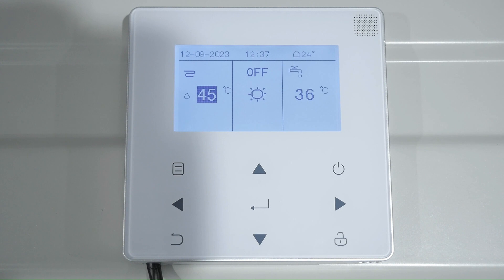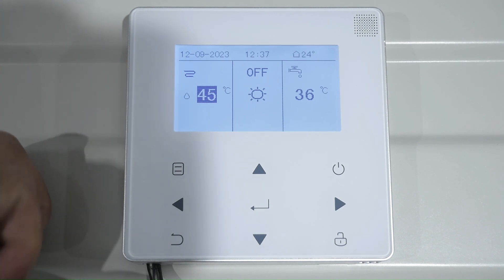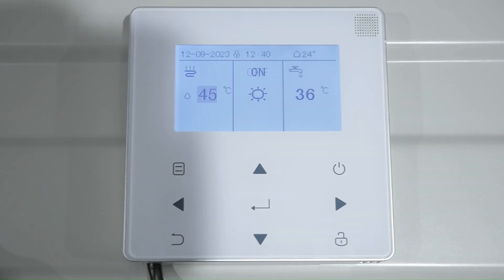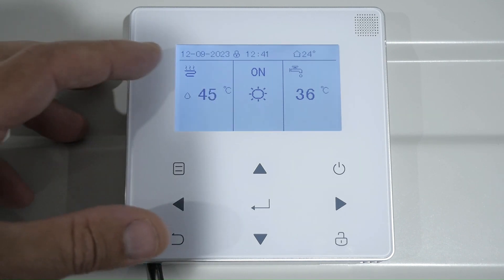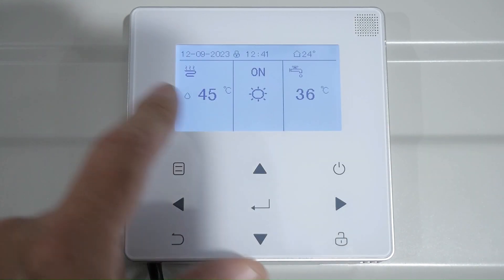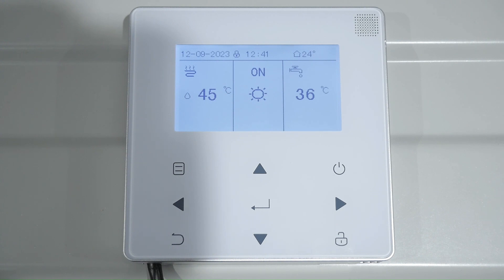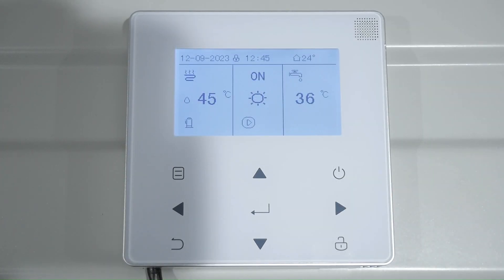You get demand on this stat which will in a moment bring the demand to the heat pump, which will in turn bring on the pump. You can see now the heating is on. It has let us know the heat pump is on and in function, and if you look for the squiggly lines you can see the function is on for the underfloor heating. In a moment you'll see a pump symbol come up to let you know the pump is starting, and then from that the compressor will run on the outdoor unit and the fan will start.